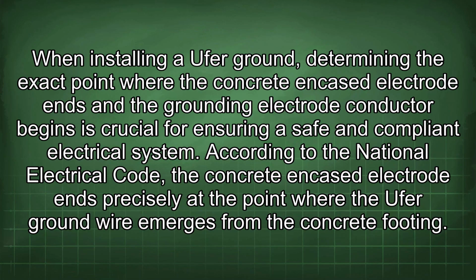When installing a Ufer ground, determining the exact point where the concrete encased electrode ends and the grounding electrode conductor begins is crucial for ensuring a safe and compliant electrical system. According to the National Electrical Code, the concrete encased electrode ends precisely at the point where the Ufer ground wire emerges from the concrete footing.